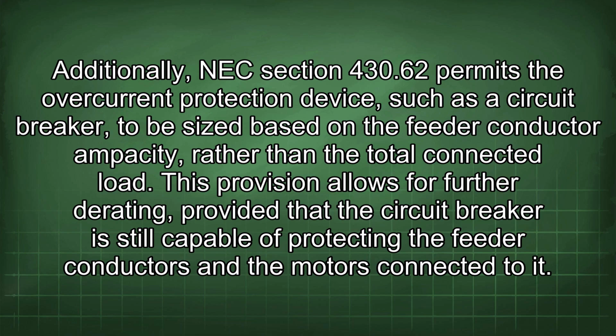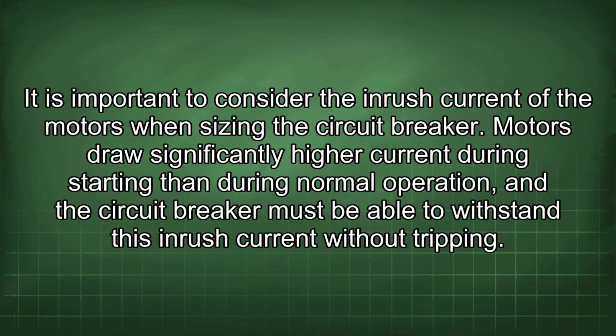Additionally, NEC Section 430.62 permits the overcurrent protection device, such as a circuit breaker, to be sized based on the feeder conductor ampacity rather than the total connected load. This provision allows for further derating, provided that the circuit breaker is still capable of protecting the feeder conductors and the motors connected to it. It is important to consider the inrush current of the motors when sizing the circuit breaker. Motors draw significantly higher current during starting than during normal operation, and the circuit breaker must be able to withstand this inrush current without tripping.